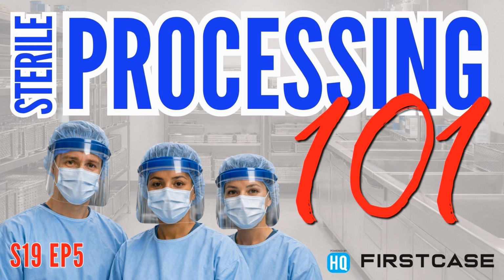Yeah. And what is the amount of time in the sterilizer that it has to be exposed to that temperature for the steam to be considered effective? Yep. So you have to follow the manufacturer's instructions. We have validated instructions provided by the people who made the instruments, tested to show that they can produce a sterile instrument, and every instrument has its own set of instructions. That being said, here in the U.S., all of those tend to be grouped around the same set of standard cycles, typically at 270 degrees with fully saturated steam for an exposure time of 4 minutes, which is about double what it takes to kill the most difficult spores. So at that temperature and pressure, you can pretty well be assured that all the microbial life is going to be dead after 2 minutes, and we sterilize for at least 4 just to make doubly sure. A big margin of safety in that steam sterilization process.